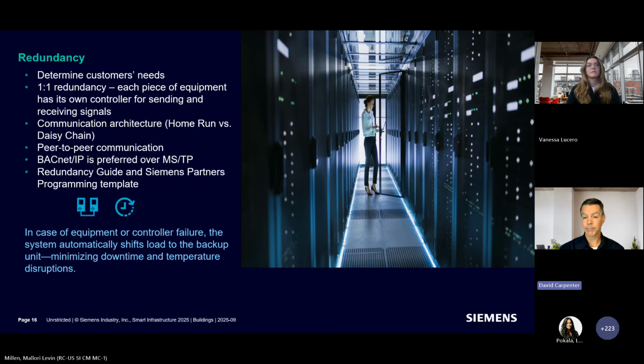Also, with the IP, we're getting data much faster than the MSTP, and we're also able to have peer-to-peer communication between controllers and real-time data that is shared from controller to controller without it needing to go through a front end or something like that. That way, every controller is aware of the points in its partner controller and is able to discern, is that point valid, or has it gone to a disturbed value, something that is no longer good, and I need to take a different course of action in its programming.